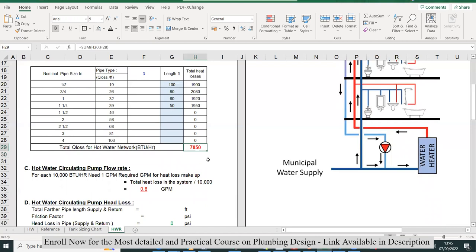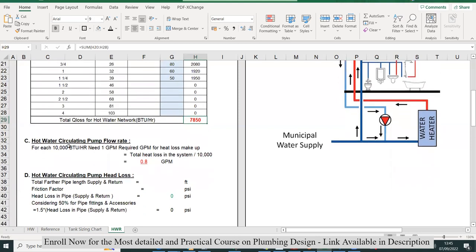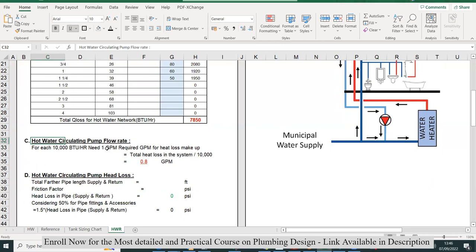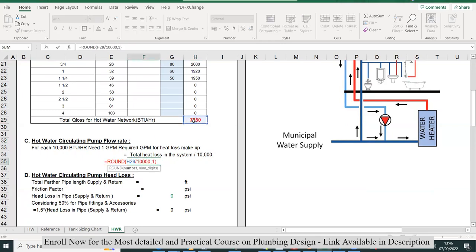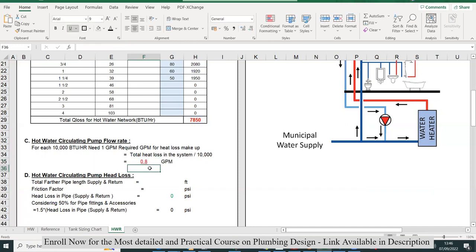In section C, we'll calculate the pump flow rate. For the pump flow rate, for each 10,000 BTU per hour, one GPM is required for heat loss makeup. We have 7,850 total, and for 10,000, one GPM is required. So I'll divide this value by 10,000. You'll get 0.8 GPM. This GPM is the flow rate of this pump. This is standard—for 10,000 BTU, one GPM is required for hot water circulation.